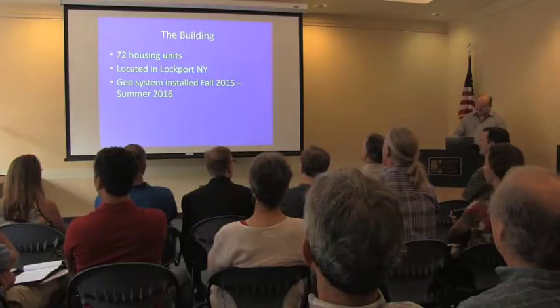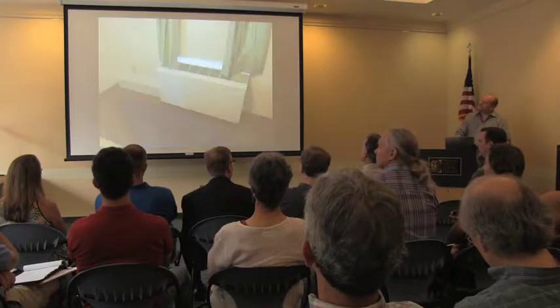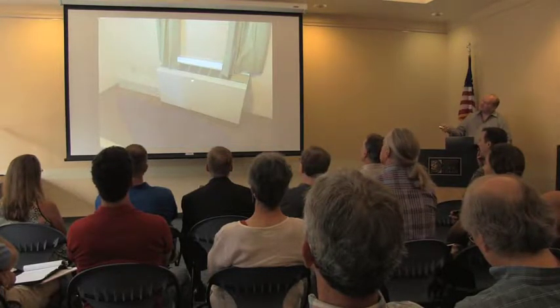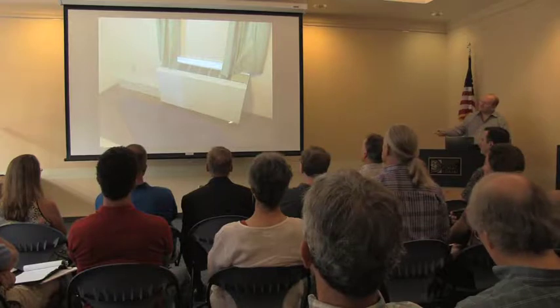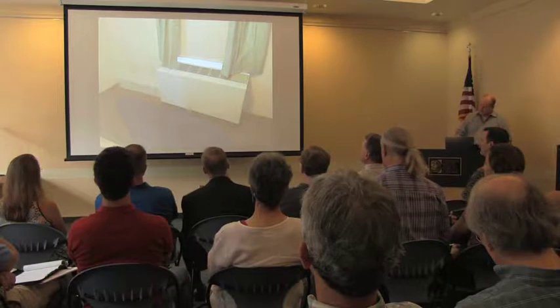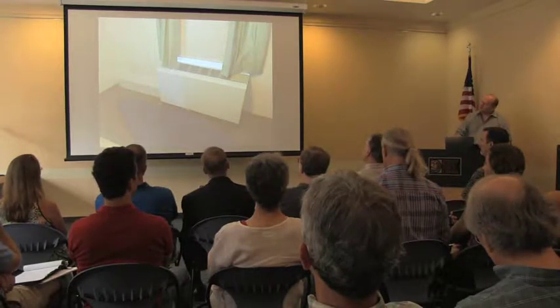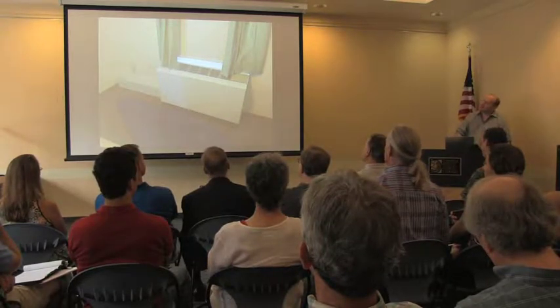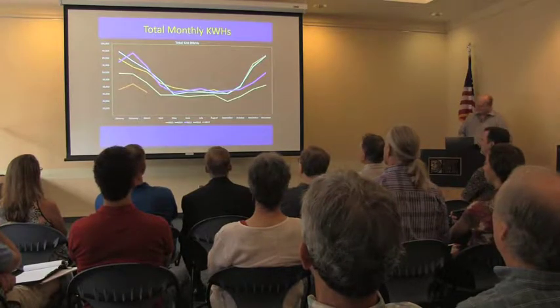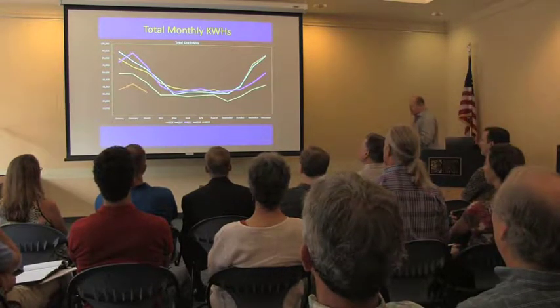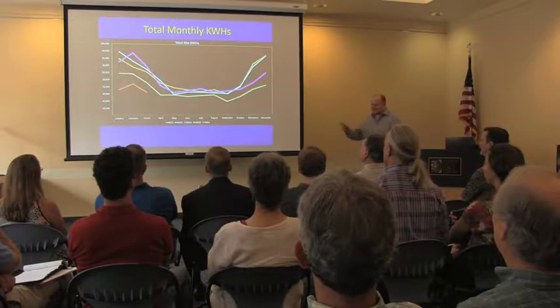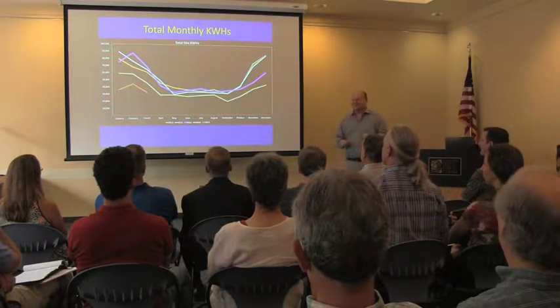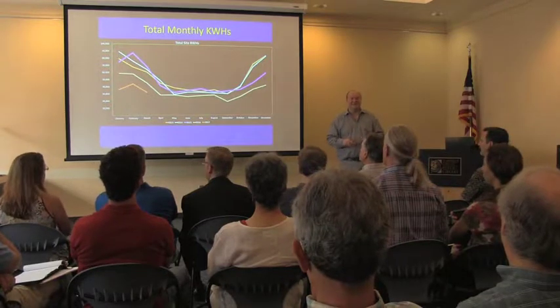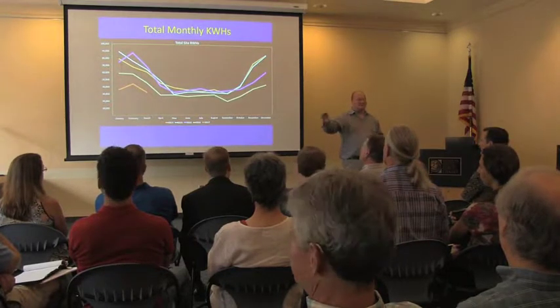So, for example, here we just converted 72 housing units in Lockport between 2015 and 2016. And we put those console units in here. These are geothermal units, and you can see the geothermal pipes come in into the apartments here. And they are two-room apartments, one bedroom, one living kitchen area, and so they have two heat pumps in total. And this is the energy usage. Again, this was unique because the entire site is on one meter. So we could answer a very simple question. What is the impact on the site if we just put in a geo system?